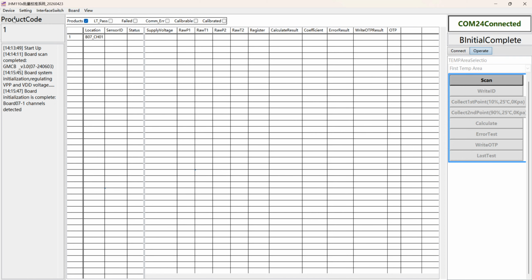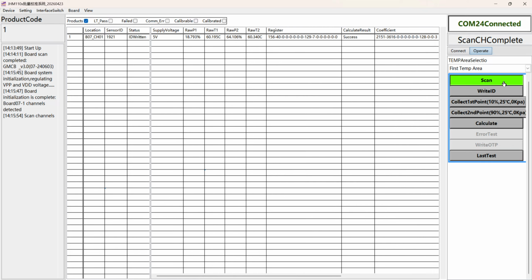Then the second is the scan. Yes, the scan. This scan is to scan the transducer to see if the transducer is properly connected to the calibration board. So we can see here, this sensor we have already written the ID, and this is the sensor ID. This sensor ID can be only written once.